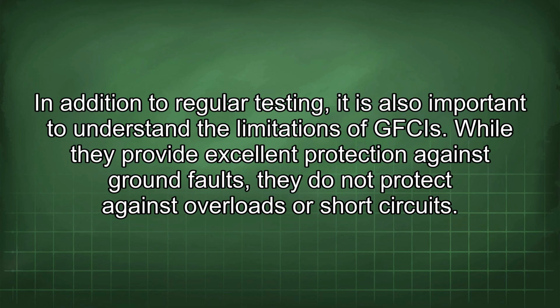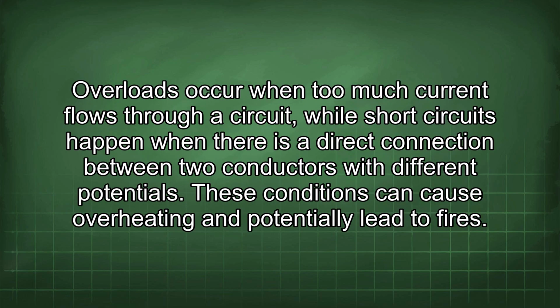In addition to regular testing, it is also important to understand the limitations of GFCIs. While they provide excellent protection against ground faults, they do not protect against overloads or short circuits. Overloads occur when too much current flows through a circuit, while short circuits happen when there is a direct connection between two conductors with different potentials. These conditions can cause overheating and potentially lead to fires.